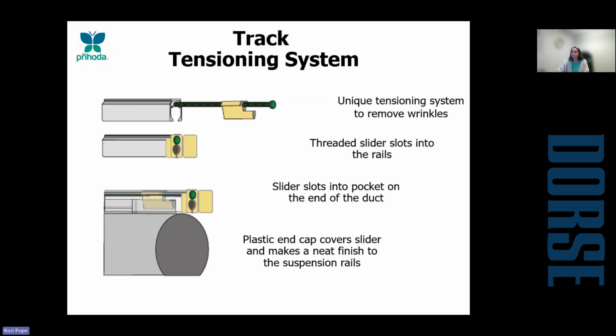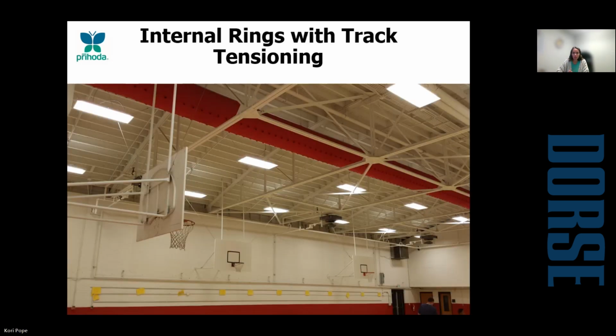So the way that this tensioning system works is you have that little yellow tab that slides down in a pocket at the beginning and the end of the duct, and then you just tension it with a screwdriver from both ends, and it'll pull the duct essentially taut. So this is a project for a gym in North Carolina where we did the internal rings and that in-track tensioning system. And as you can see from eye level, there is virtually no deflection in the duct system itself.